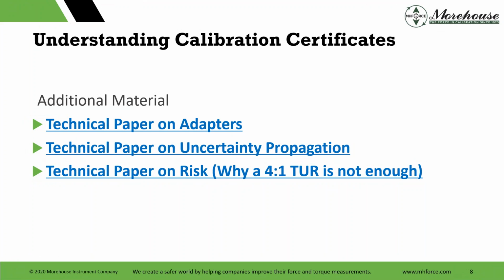Some additional reading material can be found on our website or in the PDF. We have a technical paper called Recommended Compression and Tension Adapters, a highly recommended paper. Today we are going to talk about calibration certificates, single run, pass, fail. That paper talks about the other part, the adapters, and how things interact. You could get everything right, know your device to within 0.1%, use a different adapter and have a 0.5% error. An error 5 times larger, just by switching or using different adapters. So again, that's Recommended Compression and Tension Adapters.